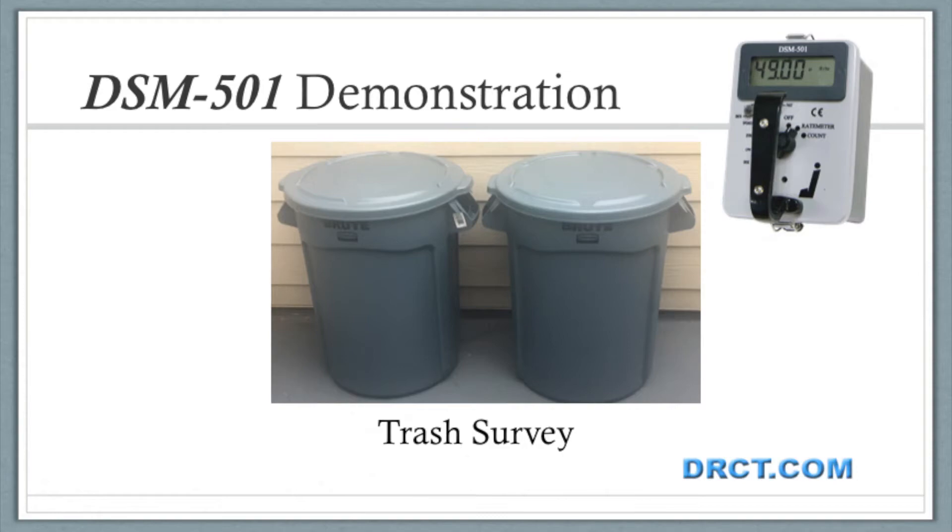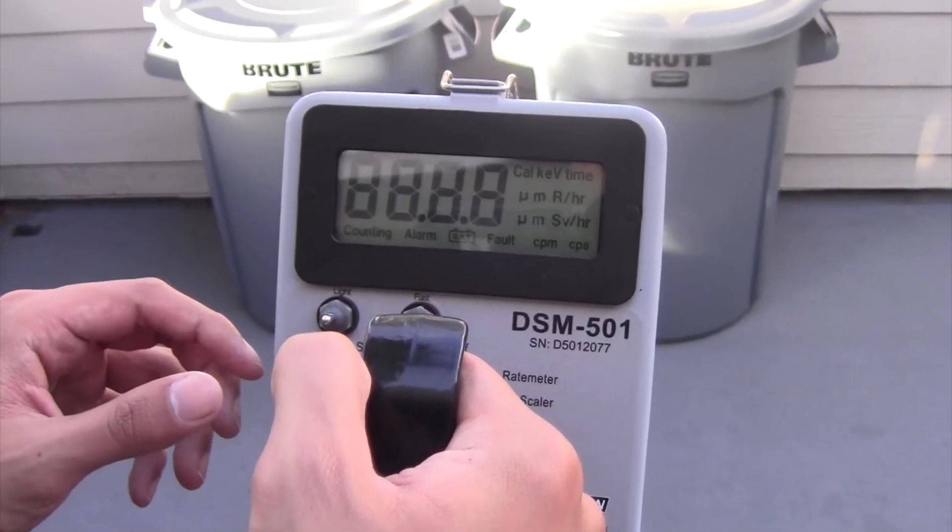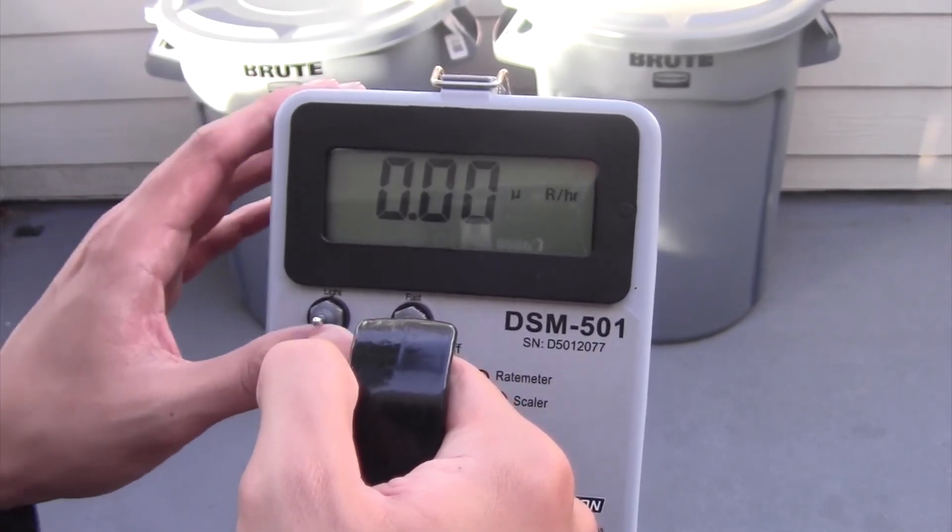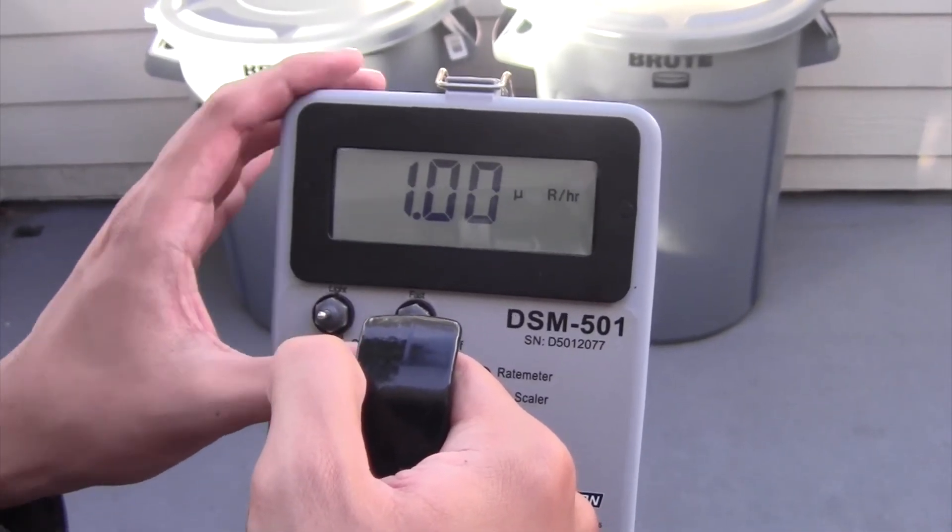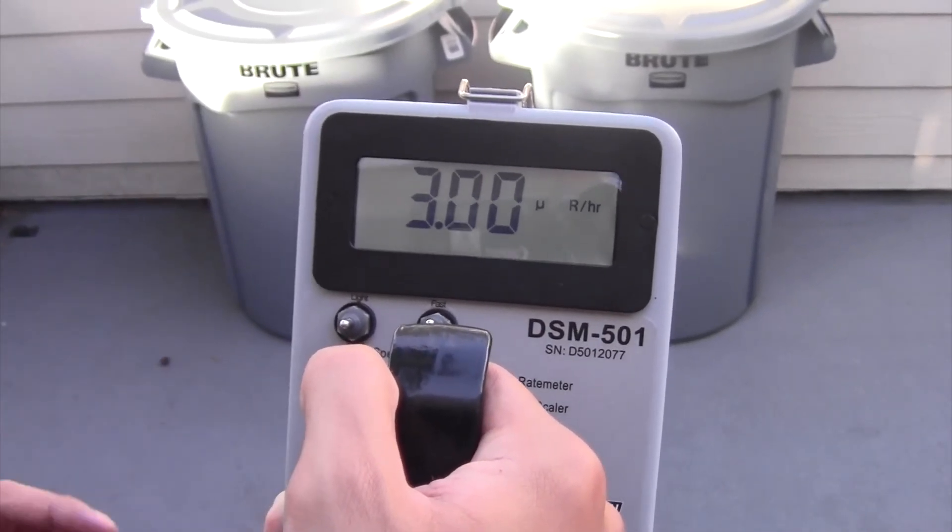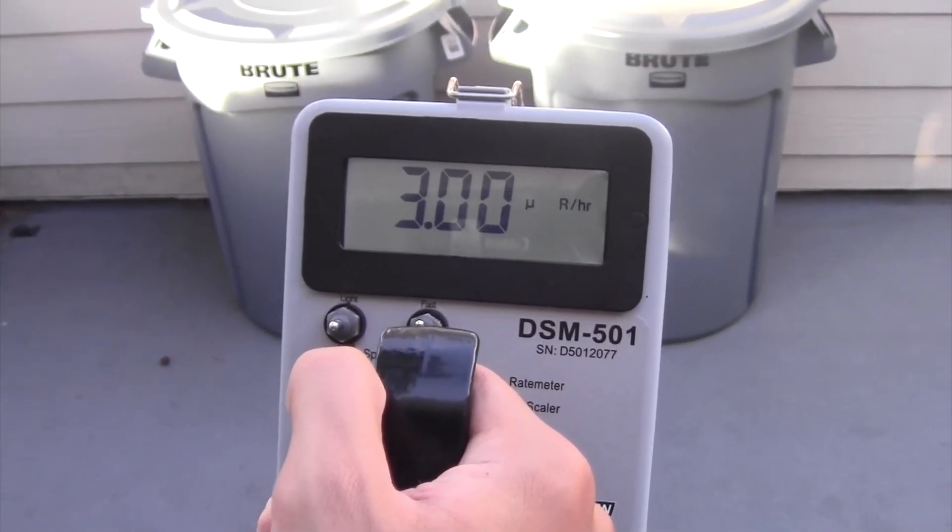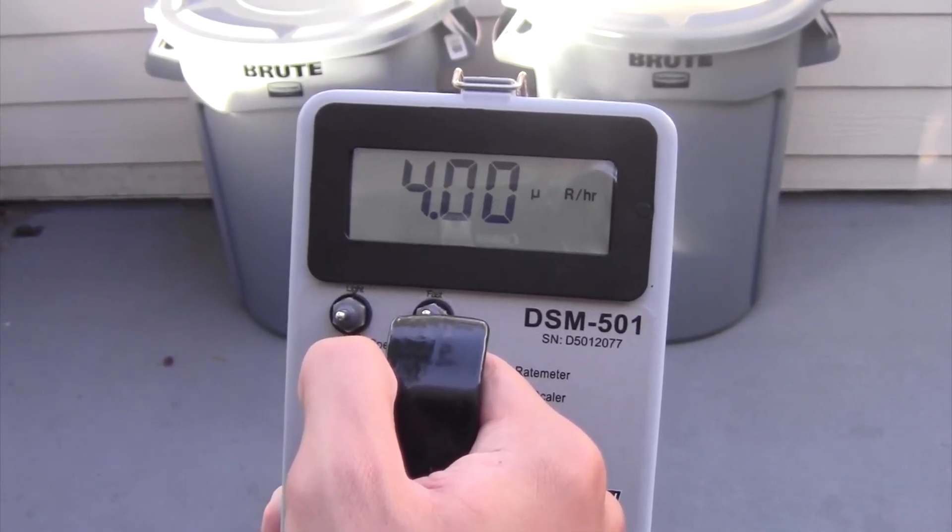For a demonstration of field use, today we will survey a bit of trash. For quick start survey, power up in rate meter dose mode. Make sure the unit is switched to fast mode and the speaker is turned on. First, observe normal background readings. We know that the operational alarm is set appropriately at somewhat higher than twice background.